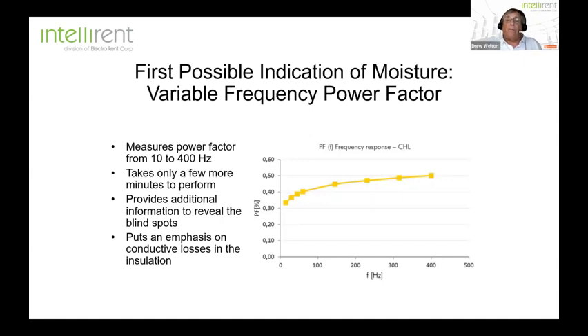thereof. So the first advanced technique I'd like to talk about is extending your power factor range, not just at 60 hertz, which we all test at in terms of measuring power factor, but also extending that frequency range either from 10 or 0 up to 400 hertz. And the one thing that I want to emphasize when we say advanced testing, it doesn't mean it's more complicated. There's plenty of testing assets out there that have the technology to do this without adding extra knowledge or training or extra time involved. So, but what does this do?